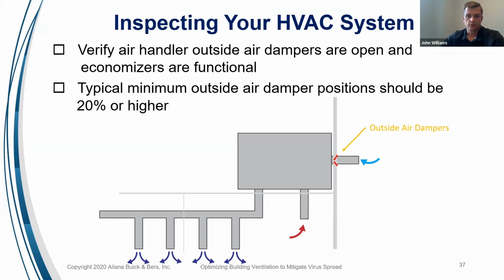Many units, whether they're chilled water or packaged DX type units, are equipped with outside air economizers. So the economizer opens up when the outside air conditions are favorable and provides 100% outside air to the building. Somebody asked a question before about opening up a gym, same idea. We're basically opening up that unit to bring in 100% outside air when the outside air conditions are favorable. That's a great way to optimize the amount of outside air we're bringing in. So we want to make sure those outside air economizers are functional.